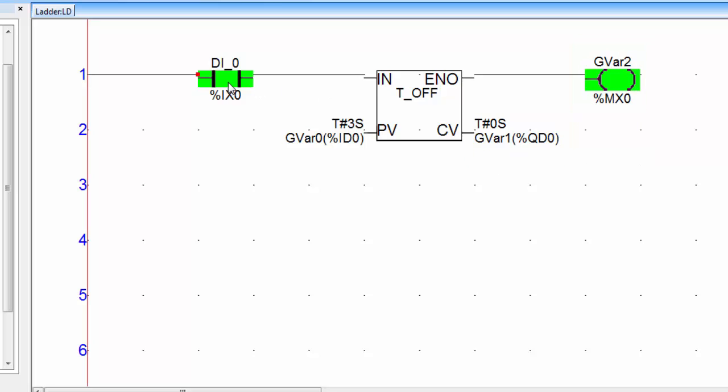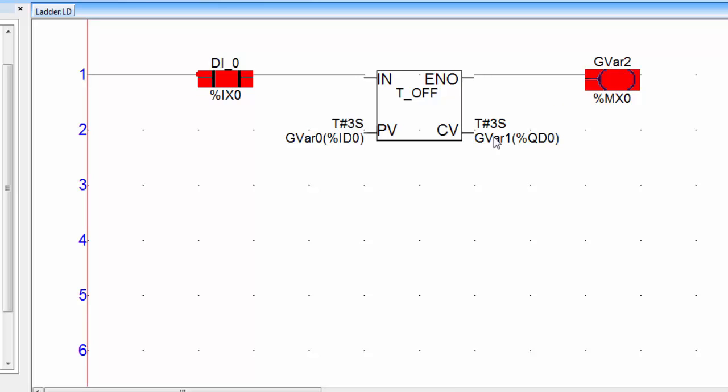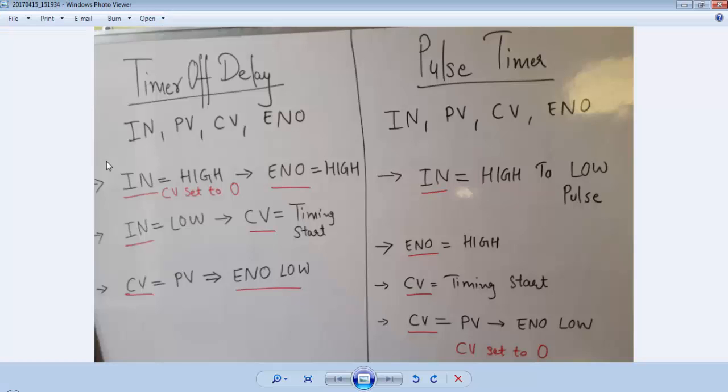Again double click on this input to release the input and you will see it will start counting the time. When the value of CV is equal to PV then it will turn off the output. A timer off delay will turn off the output after a specific amount of delay.